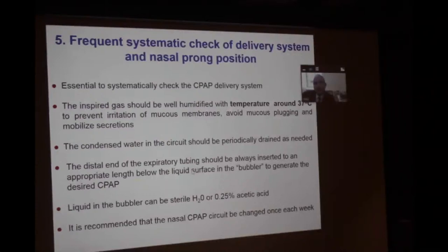The inspired gases should be well humidified, with temperature around 37 degrees, to prevent irritation of mucous membranes, avoid mucous plugging, and mobilize secretions. The condensed water in the tubing should be periodically drained as needed. One has to ensure that the distal end of the expiratory tube is always inserted to the appropriate length below the liquid surface in the bubbler so that you're generating the desired CPAP.